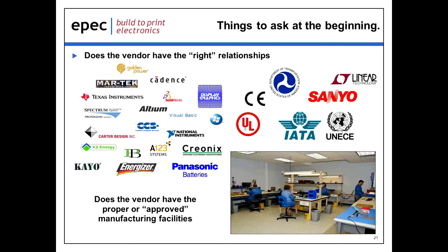And then, does the vendor have the proper approved manufacturing facilities? A lot of these companies, like Panasonic and Sanyo, only have a certain number of companies that they've approved their product to work with. And the reason, especially with lithium, is because there are fire dangers and safety hazards, as we've all seen through the recent issues with Boeing and their Dreamliner challenges.